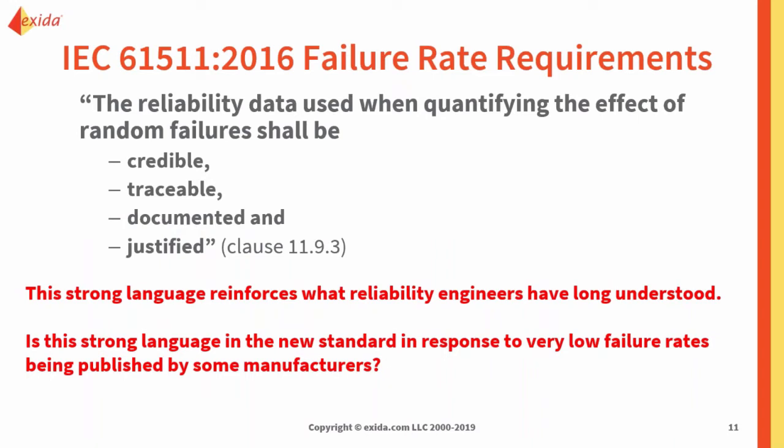It doesn't matter if you are an end user or a manufacturer. If you're using IEC 61508 or IEC 61511, both standards define failure rates and say not only do you have to use failure rates, but they need to be quality data as well. These failure rates are going into calculations, and they need to be credible, traceable, documented, and justified. In the previous editions of the standards, they just said, this is what a failure rate is, use it.